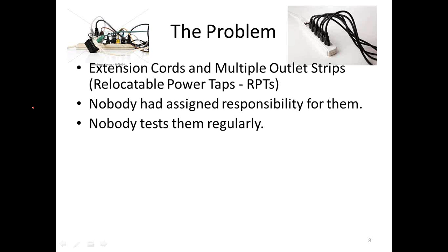They were just put in. Nobody tests them regularly, and there are many low-quality relocatable power taps that come from Walmart, the local office supply, anywhere else. These things are not hospital grade. Who knows where they're made? Who knows what kind of quality control there is? Who knows if they're made soundly or wired correctly? Nobody ever tests them. There's no incoming inspection ever done to make sure they're even wired properly or that the grounds are intact.